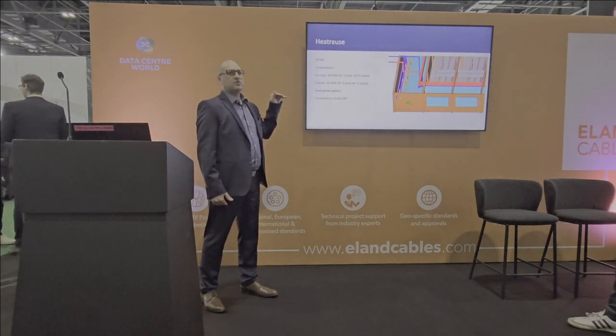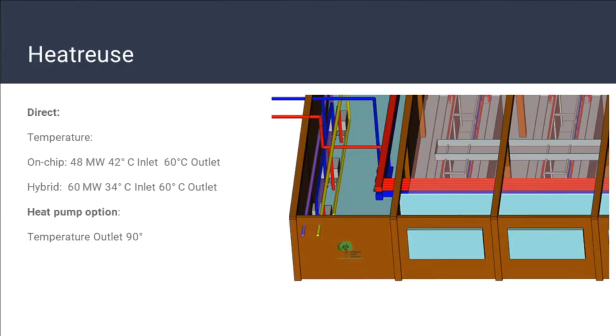First scenario is when we have an air-cooled port with adiabatic air cooler, not liquid cooler, and in that case we have only liquid-cooled chips. It is 48 megawatt, with temperature 42 degrees inlet and 60 outlet.